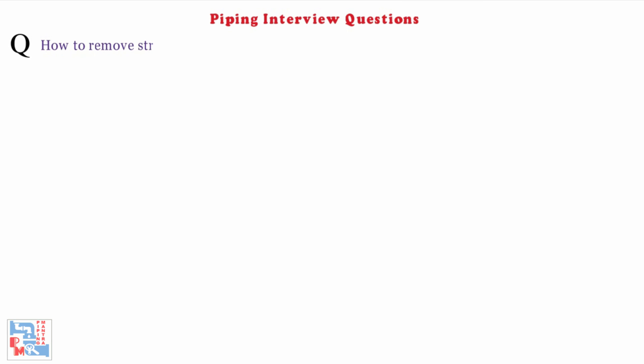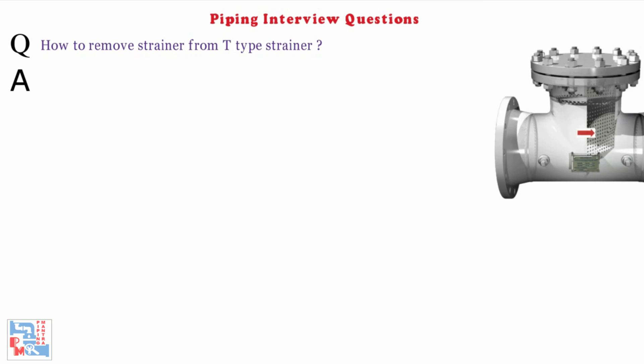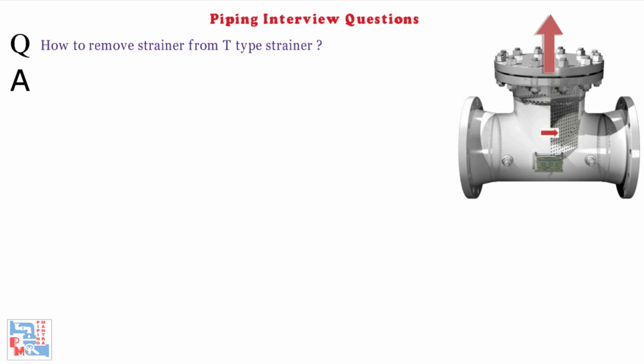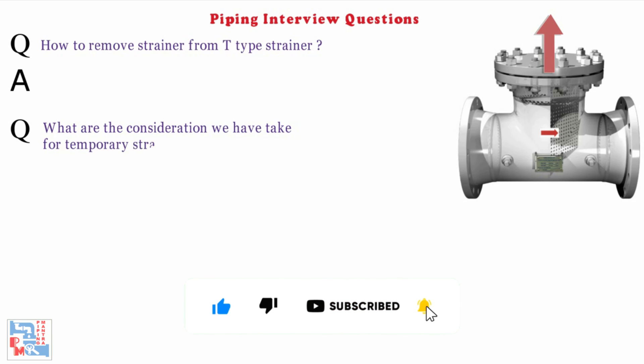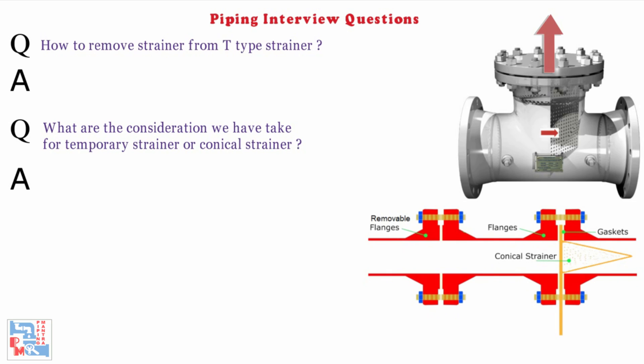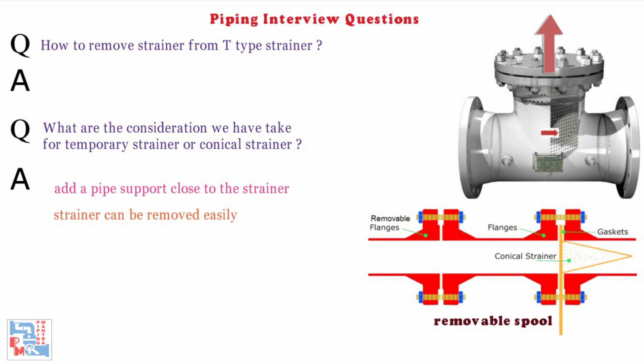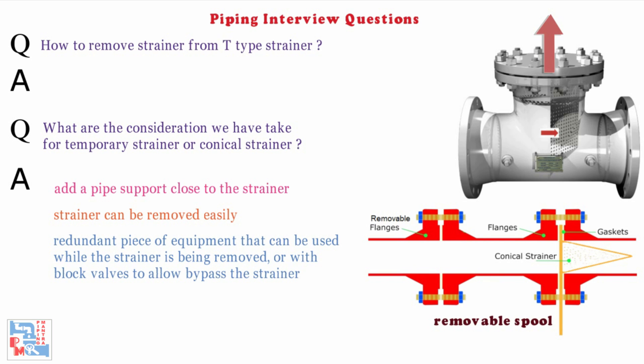Next: How to remove a strainer from a T-type strainer? The strainer is to be removed from the top, so the strainer shall be free from any obstructions. Next: What are the considerations we have to take for a temporary strainer or conical strainer? The strainer should be easily removed by adding a pipe support or pipe stand close to the strainer and/or a removable spool with a slightly longer length so that the strainer can be removed easily. It should be possible to remove the temporary strainer without shutting down the process, with the help of a redundant piece of equipment or with block valves to allow bypassing the strainer.